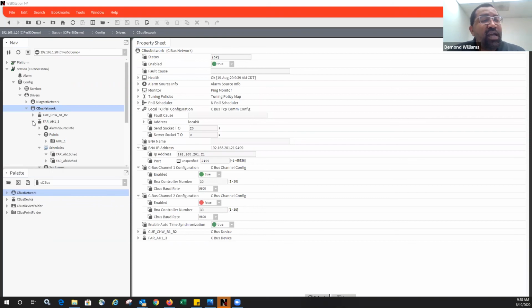Anything more than that, then you'll be looking at using another C-Bus device as well. And on that device count, does that count for like the zone controller with say 10 VAVs off of it? Would the zone controller count as one? Yes. So the zone controllers won't count against your devices. It's basically the main device itself. So if you had a zone manager on there and you had 30 VAV boxes under there, it's only going to look at the zone manager and count that zone manager as one device.